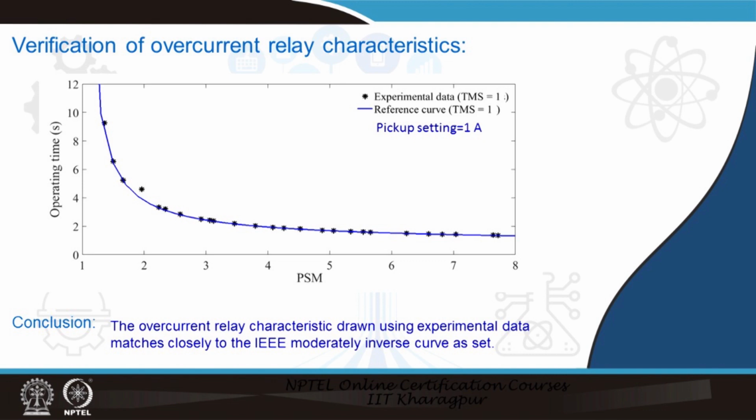That demonstrates that our experimental setup, through which we get the time recorded by the relay, and the theoretical curve do match, and that justifies that the relay performs correctly and accurately as expected. So, the verification clearly demonstrated that the relay is a proper relay, functioning perfectly as expected.